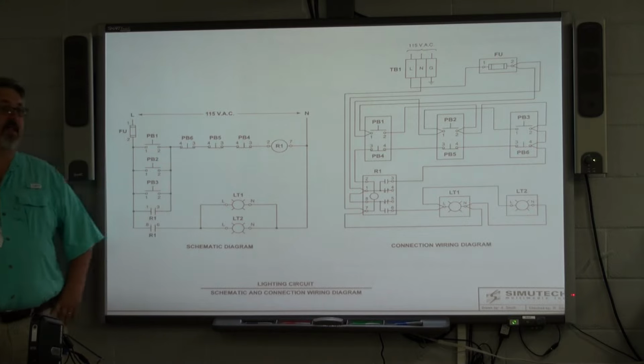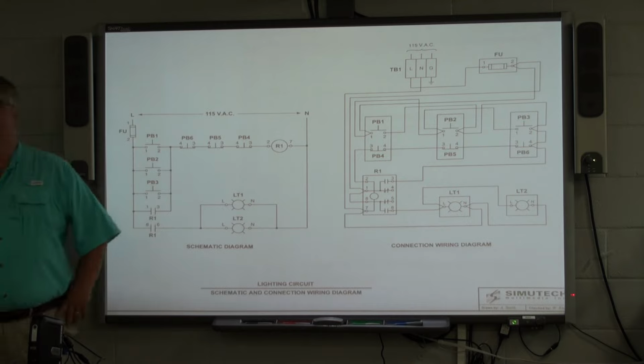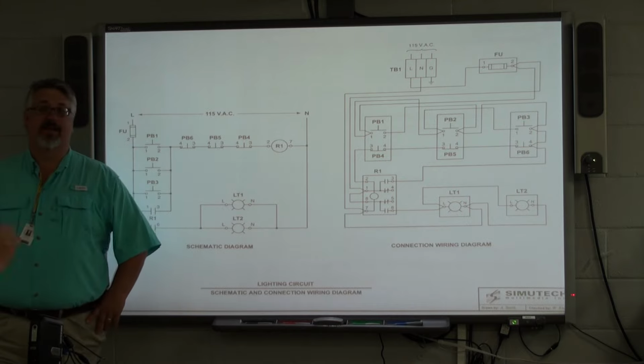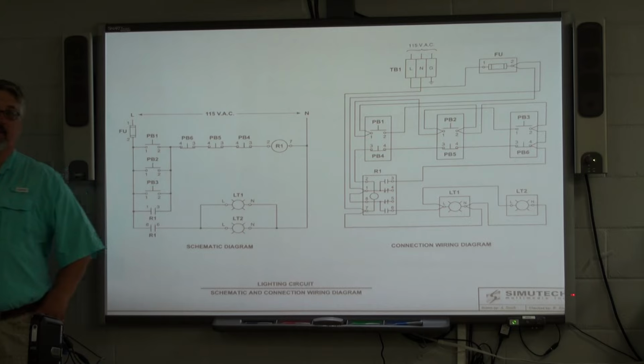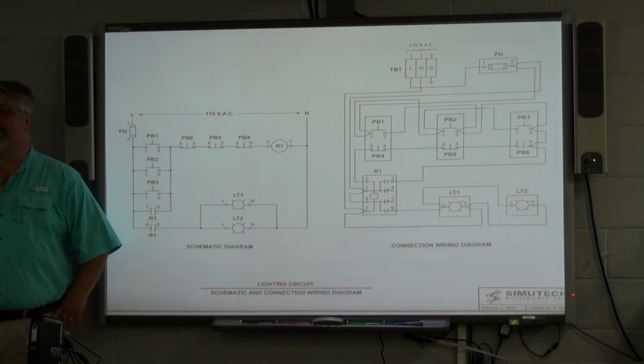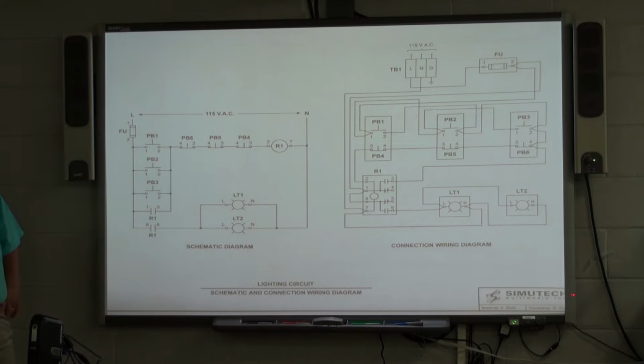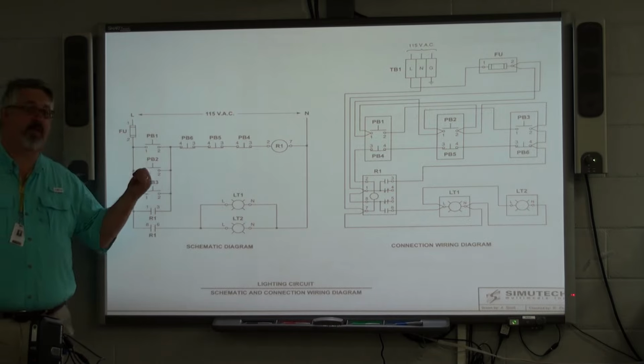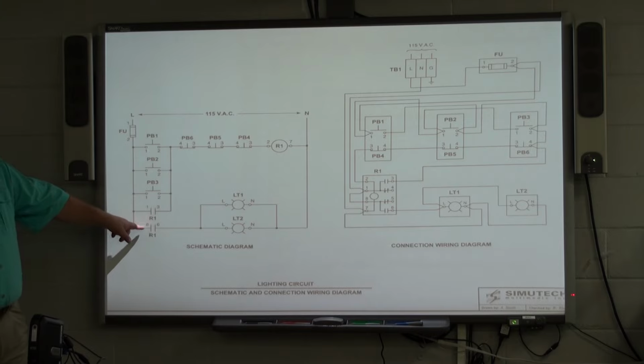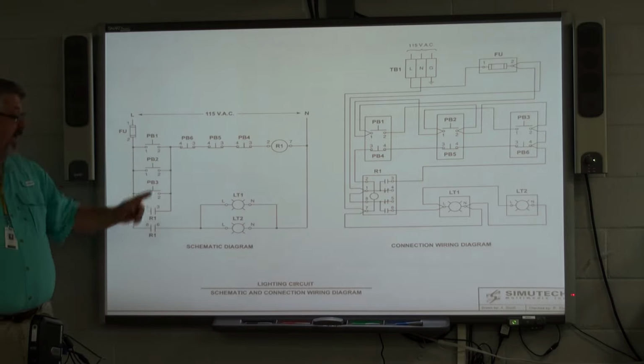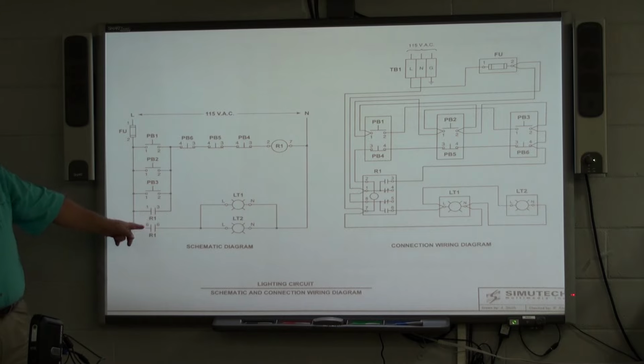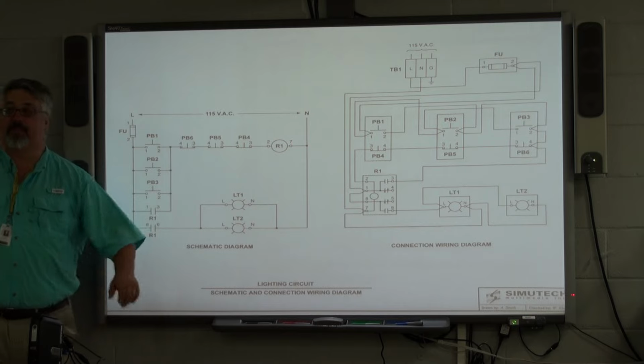Correct. Now let's look at what we're doing with the contacts. Pin 8 is the common pin of the relay on a typical 8 pin. And pin 6 is the other end, the normally open side. So what happens is, when we press that button, R1 becomes engaged, closing this contact, providing 120 volts to this light right here.